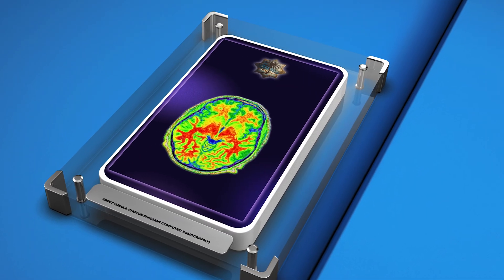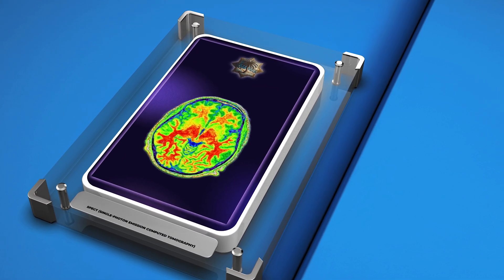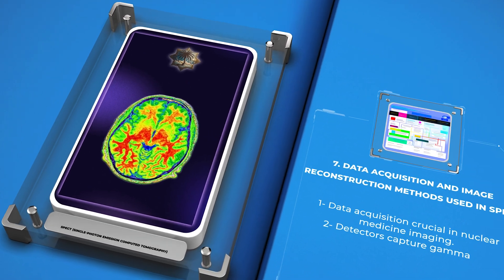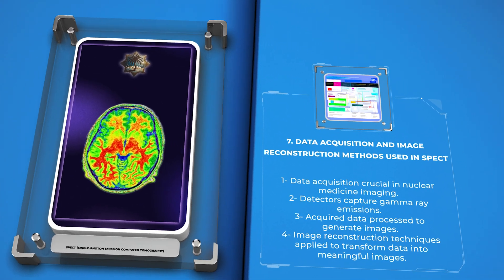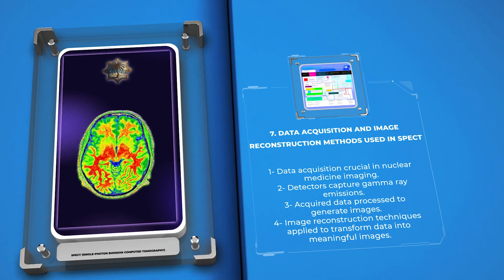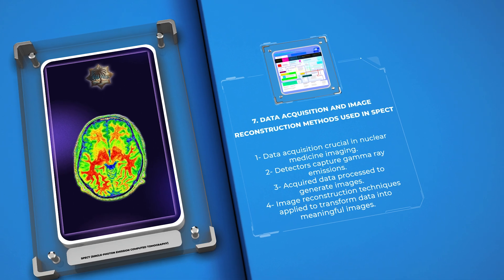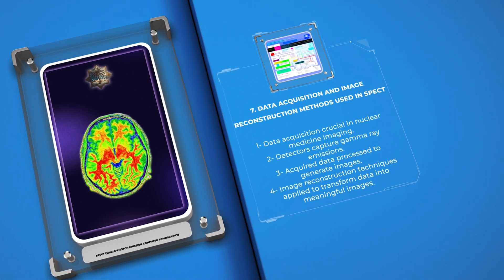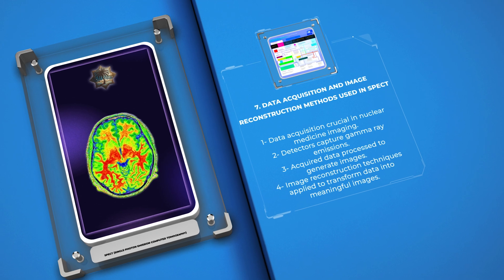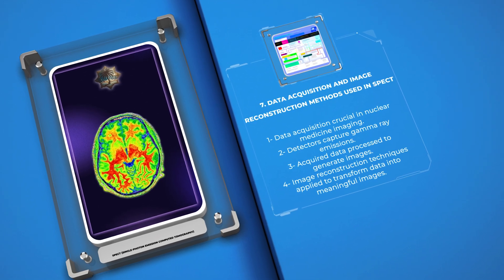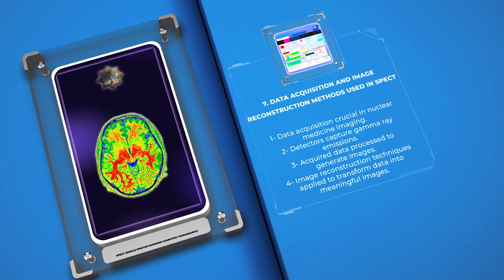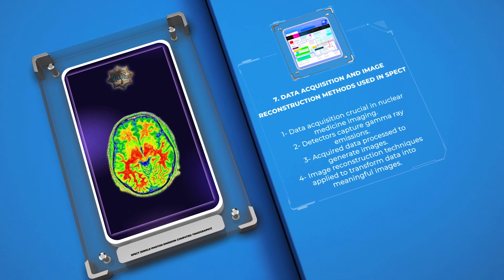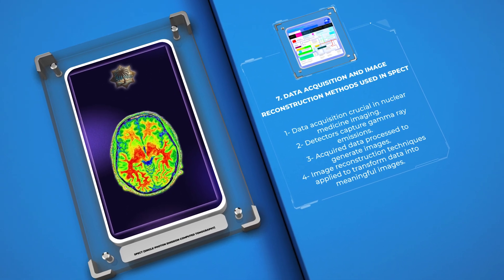Data acquisition is a crucial step in nuclear medicine imaging. The detectors capture the gamma ray emissions, and the acquired data are processed to generate images. Image reconstruction techniques, such as filtered back projection, iterative reconstruction, or statistical reconstruction methods like maximum likelihood expectation maximization (MLEM), are applied to transform the acquired data into meaningful images, enhancing diagnostic capabilities.